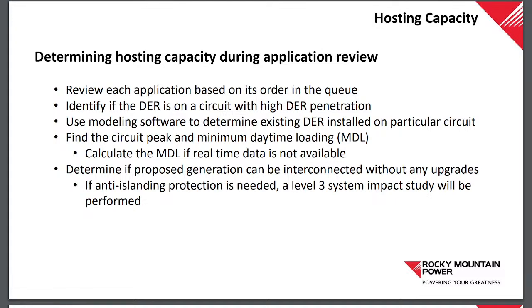But does it have to get remeasured for every application? If it has SCADA, we take the 12 months of history, find out what was connected during that time, then figure out what's been approved since that minimum was taken, and add that capacity of generation on top of the new one to calculate it. So it's a rolling 12 months? Yes.